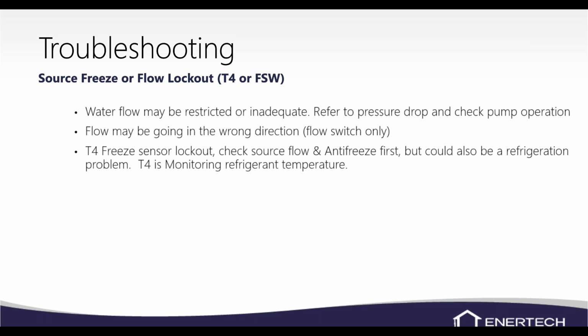On a T4 freeze sensor lockout, check the source water flow, but it could be a refrigerant problem because, again, the T4 sensor is monitoring refrigerant temperature. If you get around 50 PSI and convert that to temperature on our pressure temperature chart, that's going to be somewhere around our freezing mark. So that T4 sensor is looking at refrigerant temperature and not water temperature. So it could be a low pressure problem and not an actual flow problem.